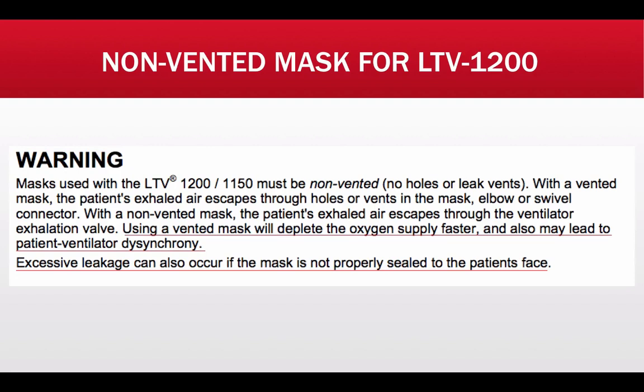I want to stress something very important here. If you arrive at the floor with a brand new tank at 2000 PSI and as soon as you transition the patient to your ventilator and oxygen supply the tank is nearly depleted in five minutes, the reason is that a vented mask with holes is sensed as an air leakage by the ventilator. The ventilator then overcompensates and starts to utilize excessive oxygen supply, which is why a 2000 PSI tank can be fully drained in a matter of minutes.